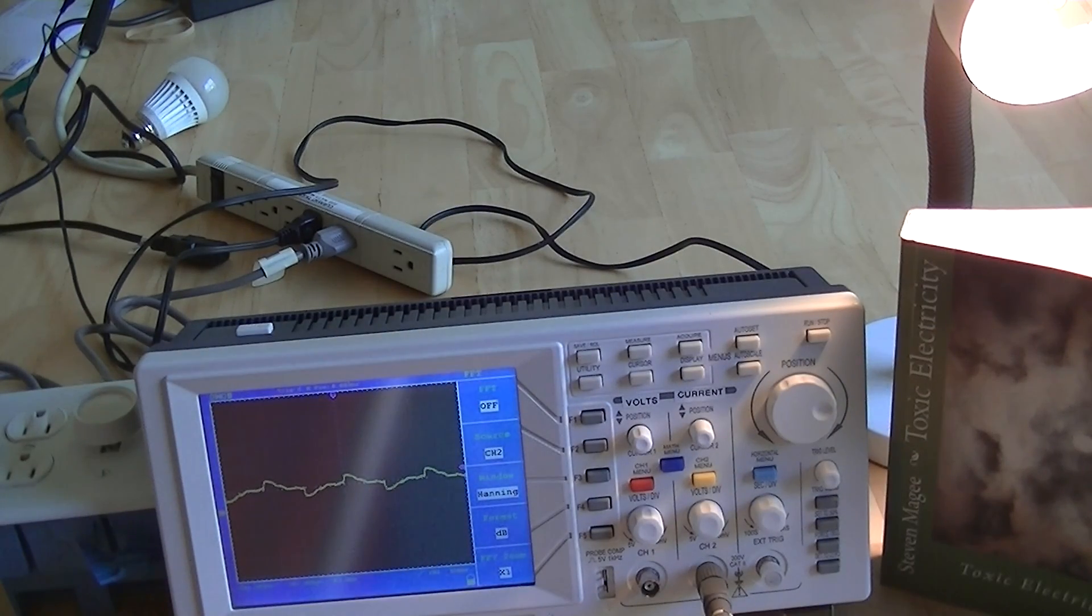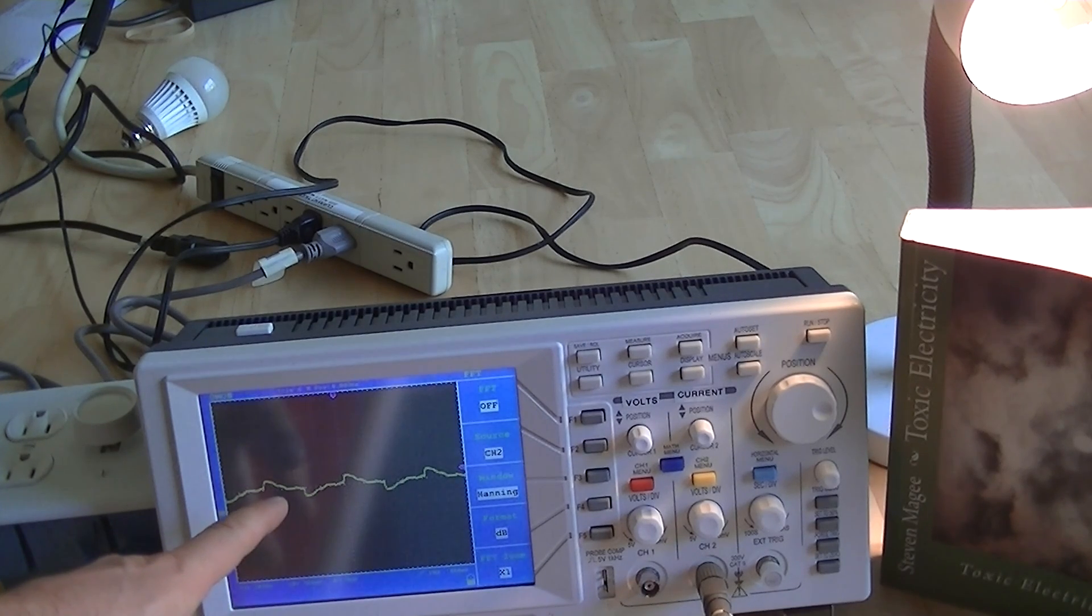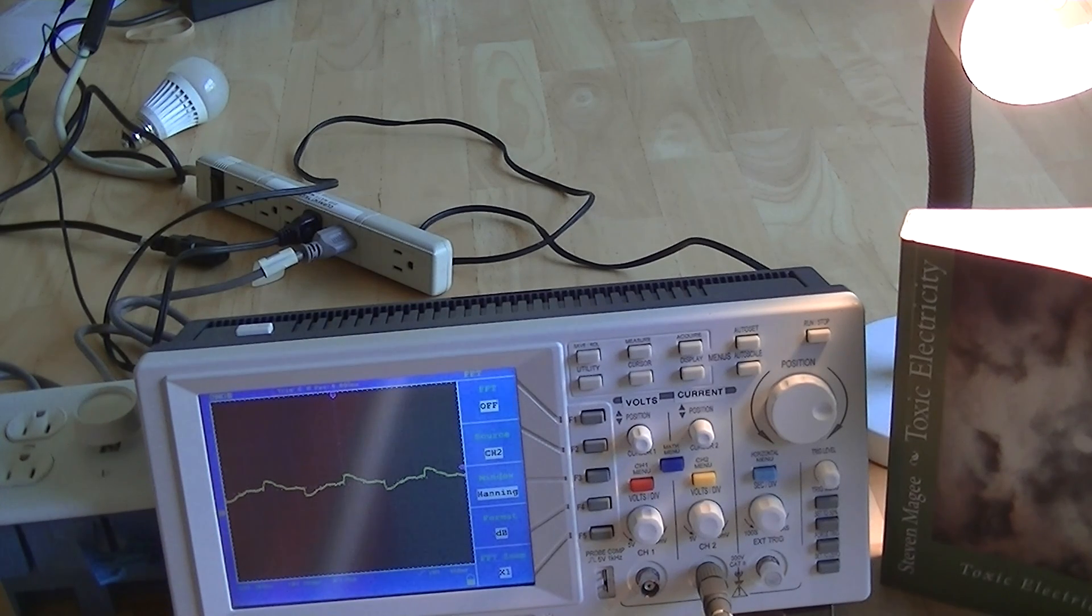So this particular LED light bulb is connected to the main system right now. We actually have the oscilloscope recording the current waveform going out to that light bulb and as you can see it's highly distorted. So that causes harmonics.